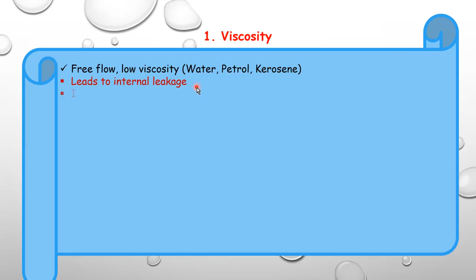If a fluid flows freely, it means the fluid has low viscosity. The examples of fluids which have low viscosity are water, petrol, and kerosene. So what happens if viscosity is very low in case of fluid power systems? It leads to internal leakage. There will be an increase in temperature and excessive wear due to breakdown of the oil film. These are some of the disadvantages of hydraulic fluid if it has low viscosity.